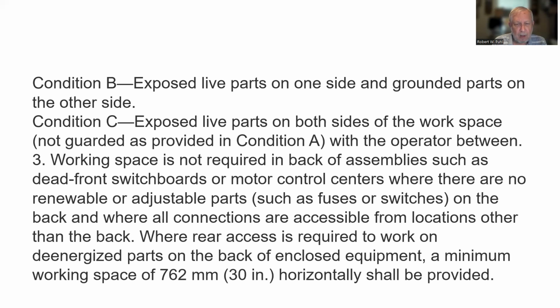Three, working space is not required in back of assemblies such as dead front switchboards or motor control centers where there are no renewable or adjustable parts such as fuses or switches on the back, and where all connections are accessible from locations other than the back. Where rear access is required to work on de-energized parts on the back of enclosed equipment, a minimum working space of 30 inches horizontally shall be provided.